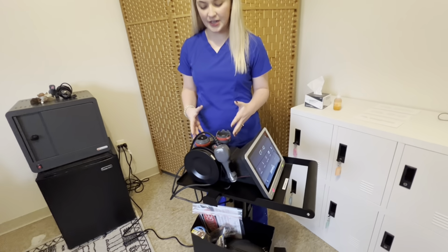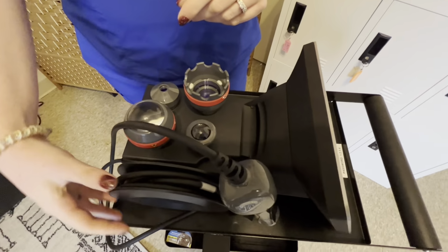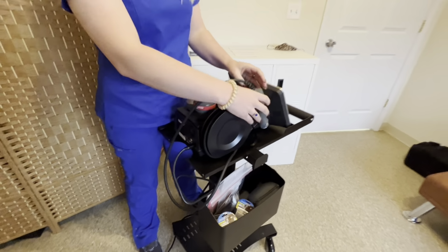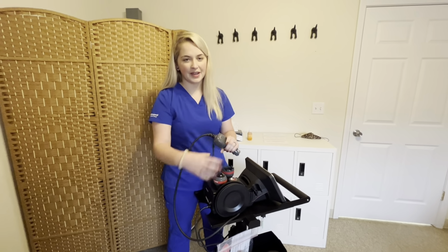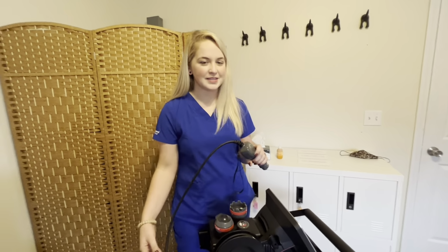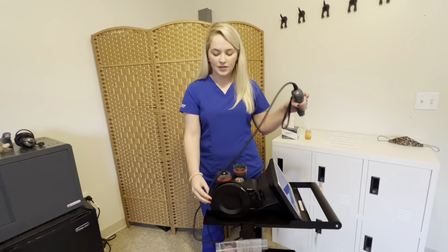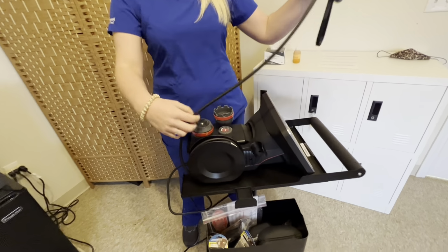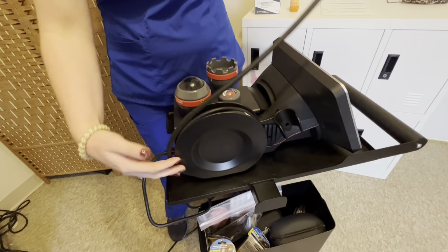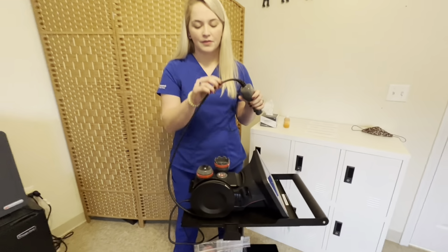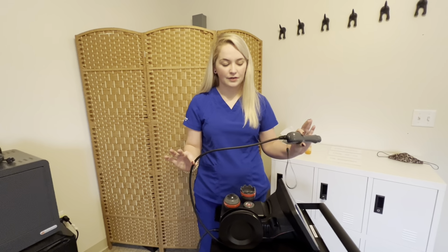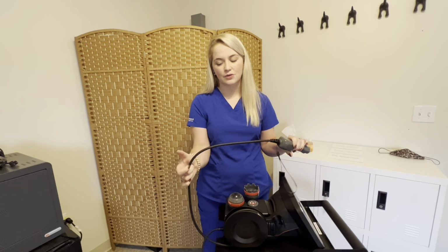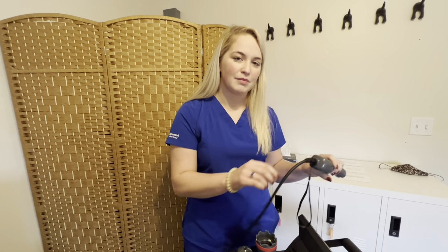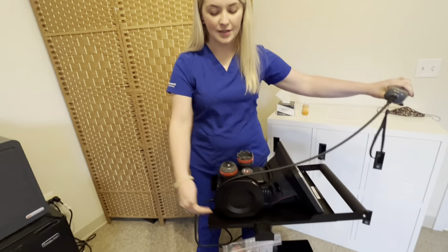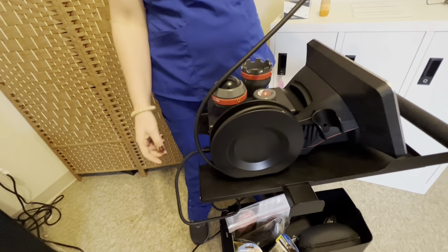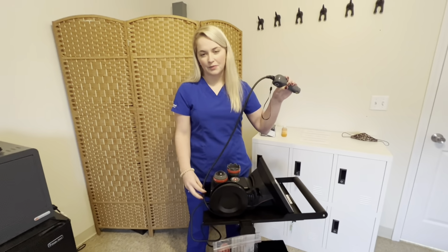The back portion of the machine is a little bit different than our old one, as you can see. On the side there's this wheel, and for the handpiece itself, that is where its cord is going to be housed. So it's not a bunch of cords wrapping around the base of the machine; it's all going to be stored here. We really want to make sure when we're housing this back, we are appropriately wrapping the cord around this wheel, so that the transfer of treatment is not broken or damaged, because if this cord is kinked, the delivery of the treatment is going to be altered. So make sure that when we're wrapping this back up, we're not kinking it, and we're not rolling over it with the wheels of the machine. It's stored back appropriately here.